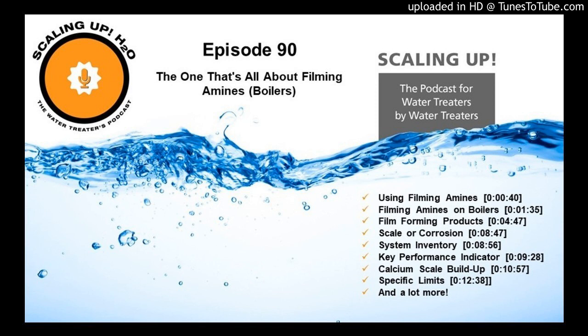If there's an issue, let's say it's a scale issue, right? Let's say you have a really scaled situation. There's a boiler that has inherently struggled with softener upsets. And over time, you just have a calcium scale buildup. Okay, well, we can go in and we can constructively work to clean that out. But we all know with scale deposition like that, there's potential for underdeposit corrosion, right?